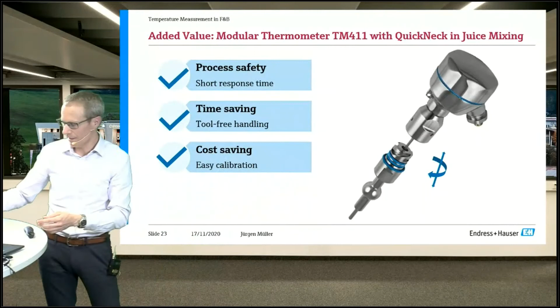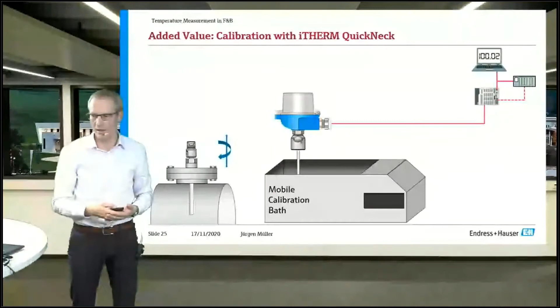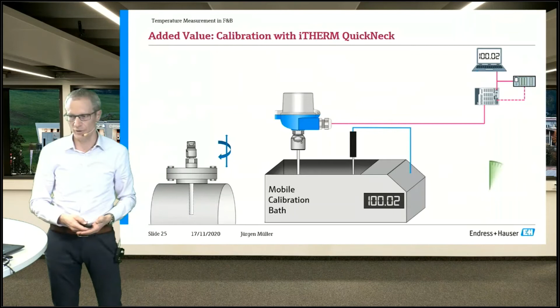I have another slide here to show again the straightforward calibration process with a Quick Neck. As indicated before, you remove the sensor from the thermowell, put it in the calibration bath, add a reference, certified reference thermometer into the bath, and do the calibration. This whole process, with the Quick Neck available, is so fast that it leads to cost and time saving.